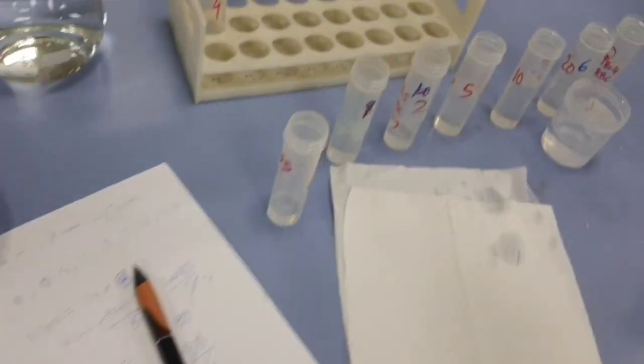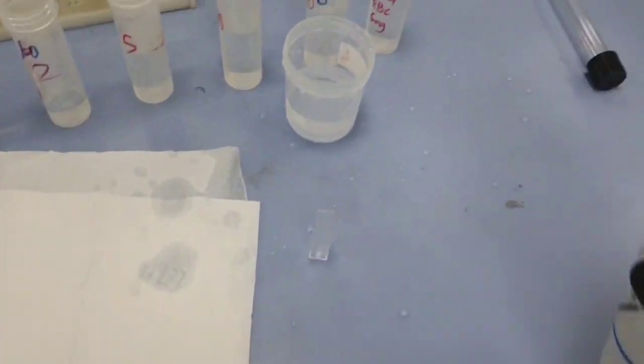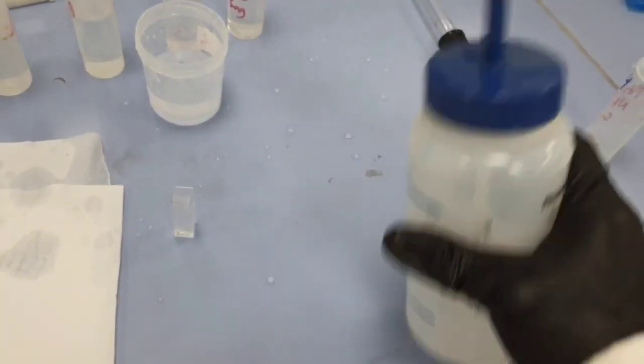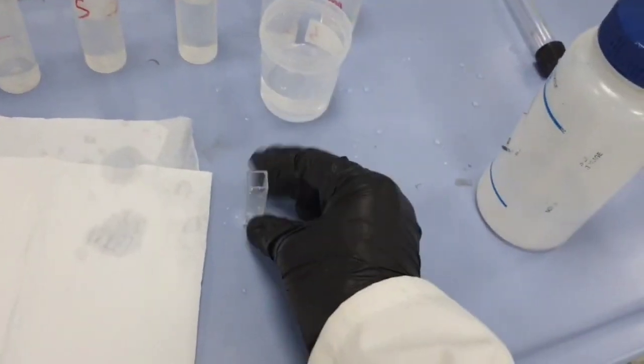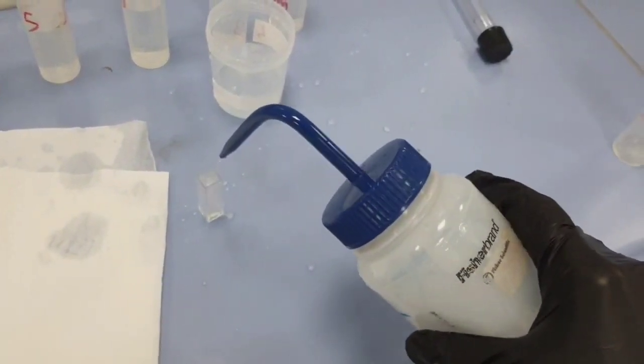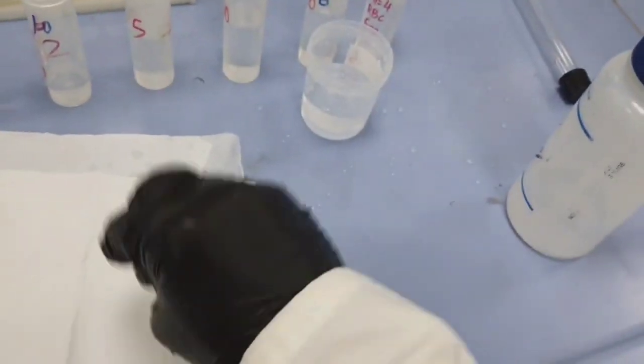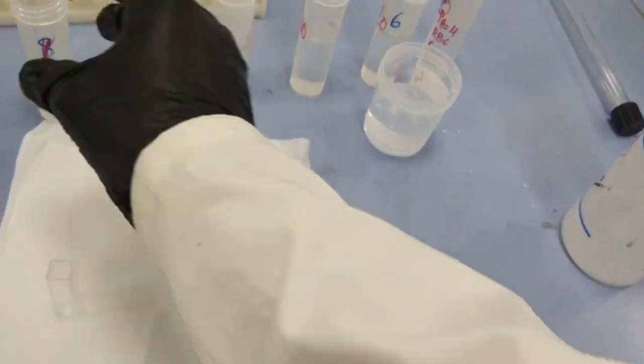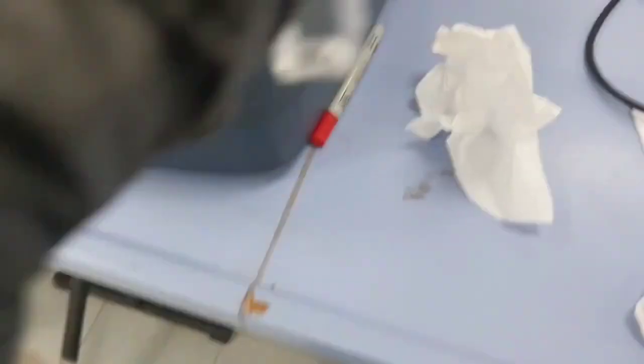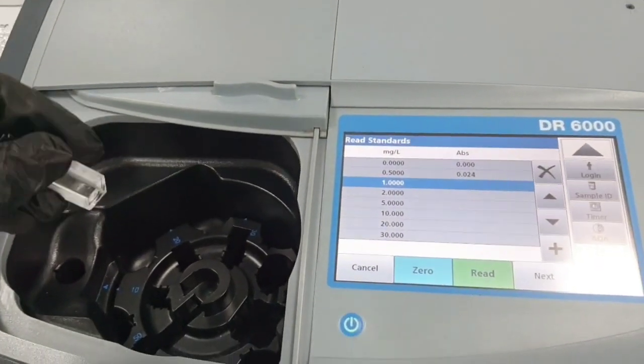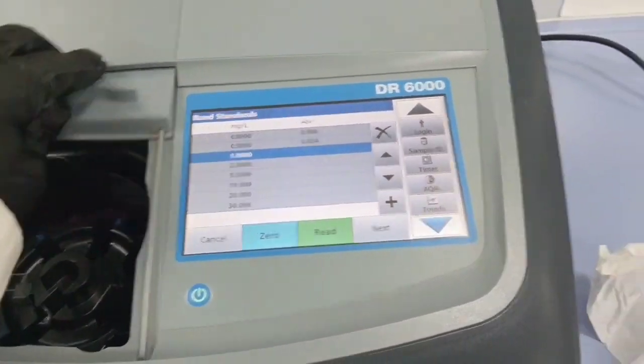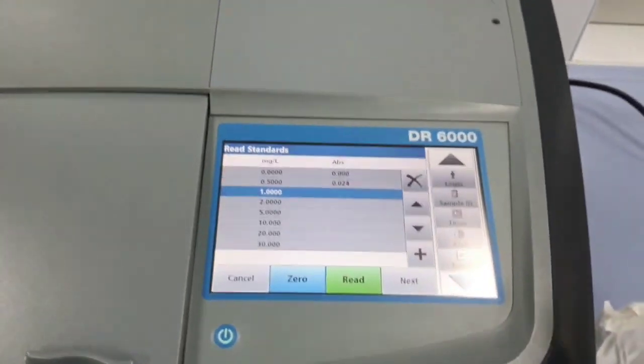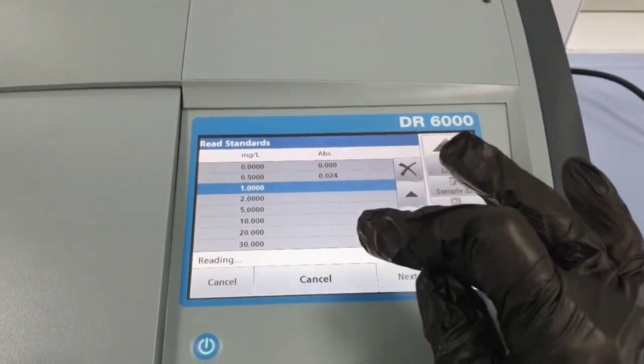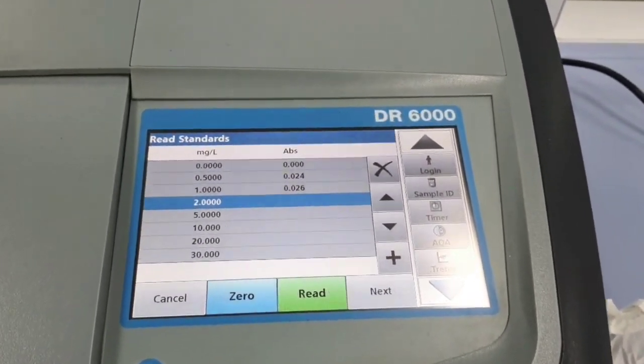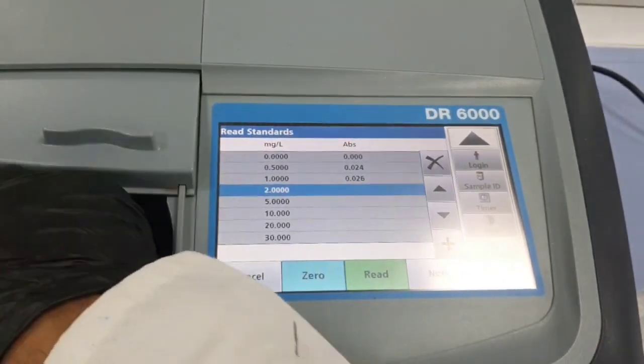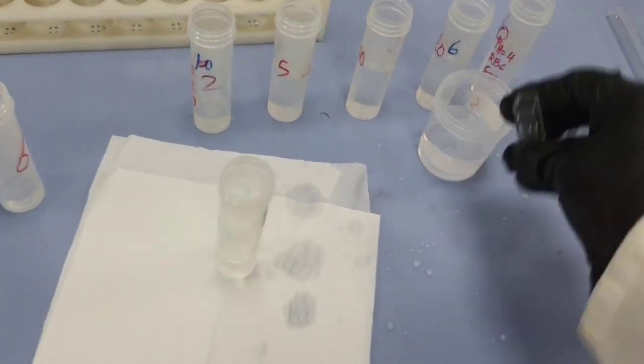Similarly, I will discard this and add the next one. First I will rinse the cuvette. After cleaning, I add the cuvette here. If 0.5 is reading 0.024, then for 1 the absorbance should be double. I'll press read. It's not double, but it's more than that, so we will check what the issue is. Let us do it one by one.